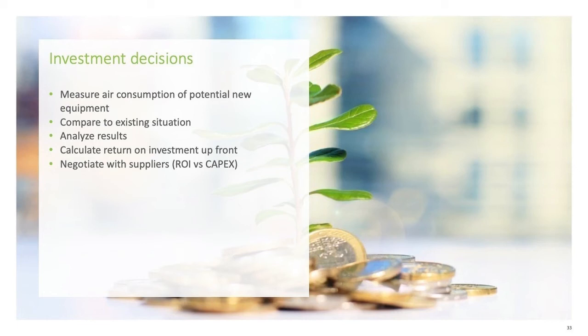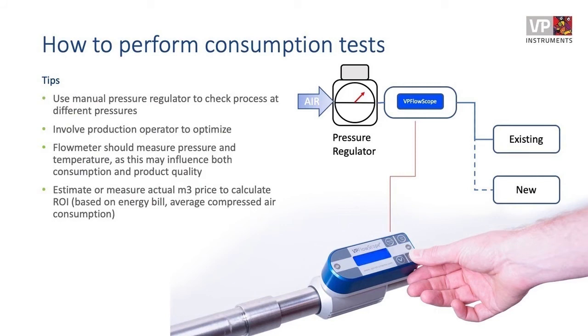So how does it look? Well, you need a few components. You need a flow meter, obviously, one that also measures pressure and temperature. You will need a pressure regulator. And you need one of the people operating the production equipment, because it's important to also look at the quality of the new process. Is it still up to the quality standards you want to achieve in production? Then basically it's connecting the air nozzle instead of the existing open blow, and maybe another one, and comparing those, and also looking at different pressures. If you feed it with lower pressure air, it might do the same job as well, or maybe even better.